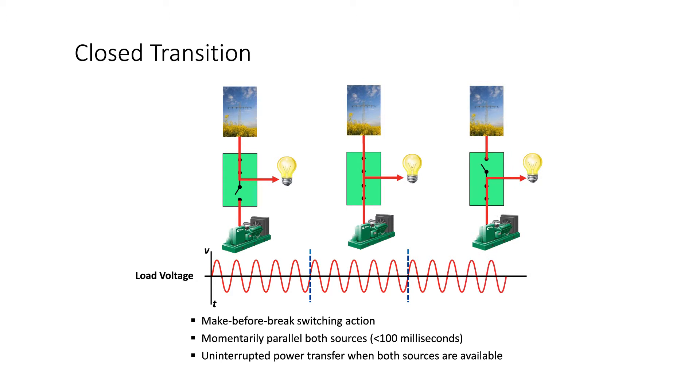Because closed transition involves momentarily paralleling with the utility, utilities often require additional protective functions when closed transition is applied. In order to achieve closed transition with the transfer switch, the hardware of the ATS must be capable of closed transition operation.